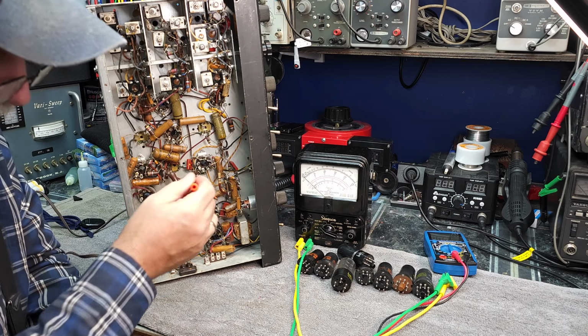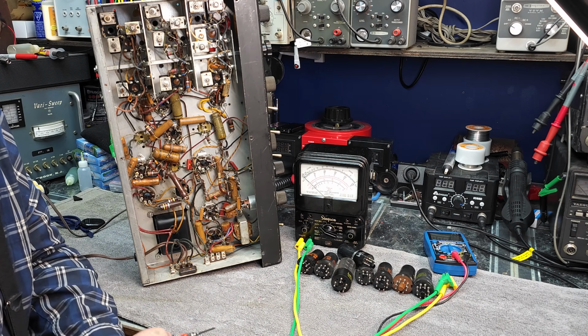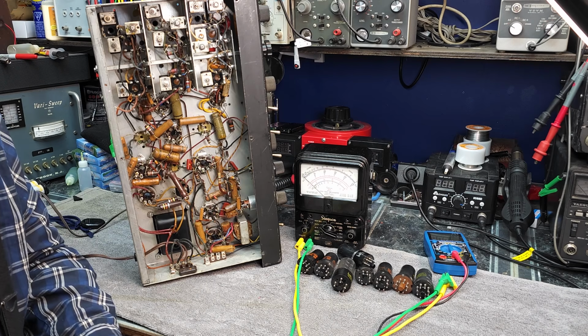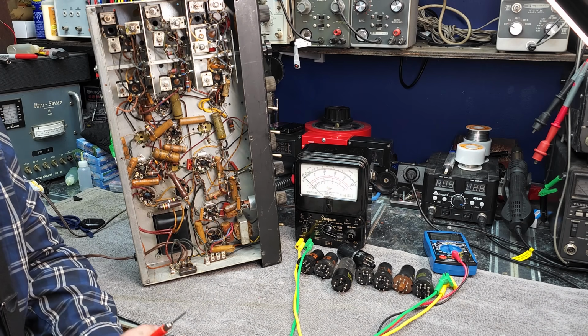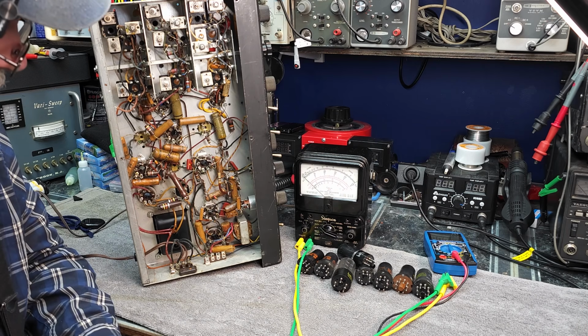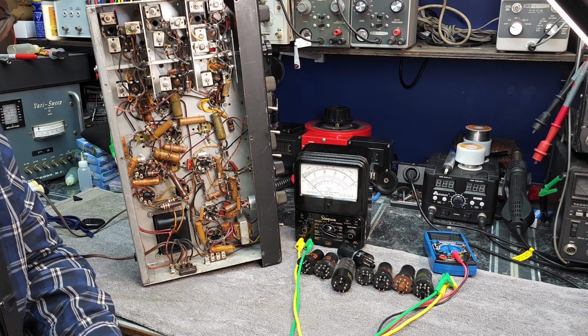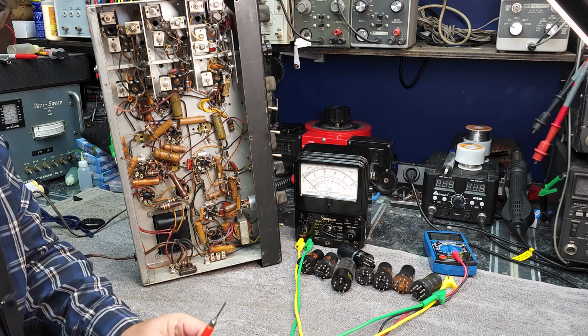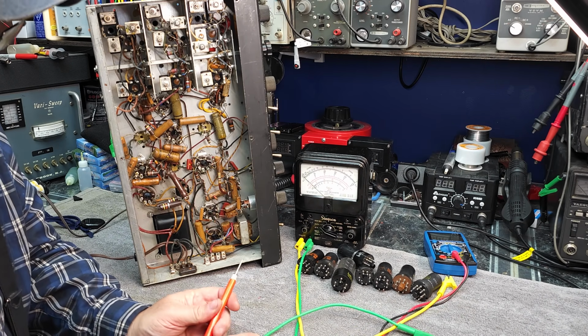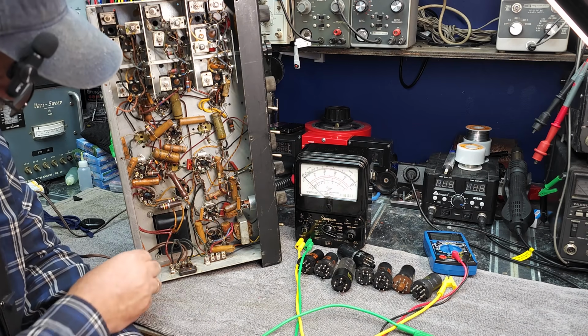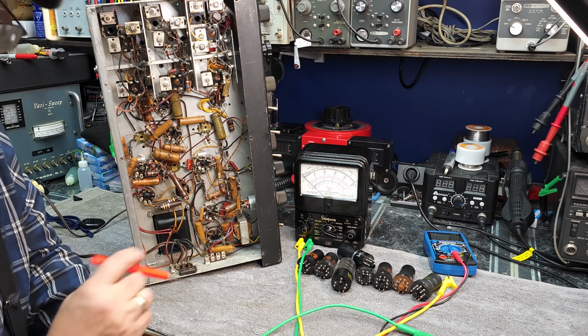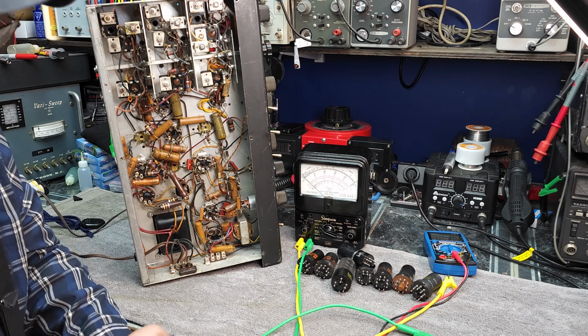This capacitor has the potential to store 360 volts DC, and that can still be present well after you turn the machine off. You can get a serious shock, all the way up to being lethal, if you're not careful and don't discharge that capacitor—or if it sits on the shelf a long time it may slowly bleed off. Having what I call a 'Jesus stick,' a test probe with a ground clip and a resistor in the path, lets you clip onto ground and touch each terminal to short out or safely drain that capacitor.